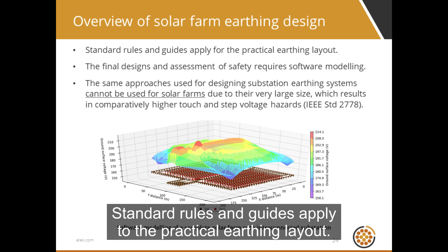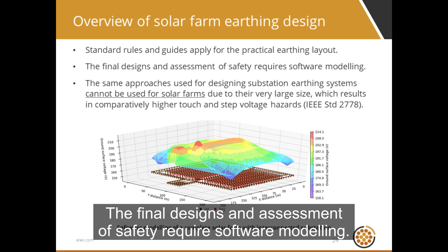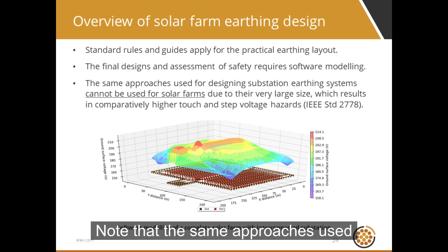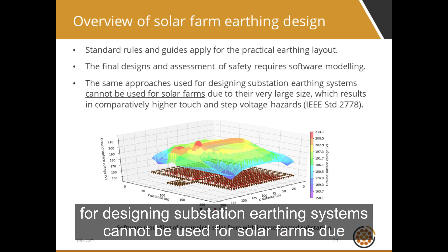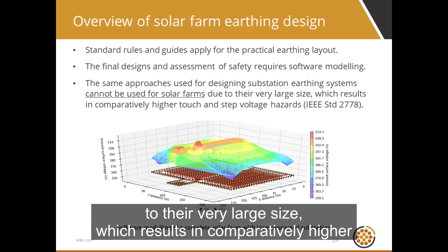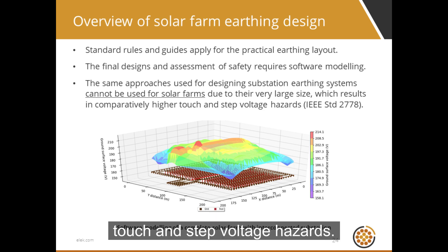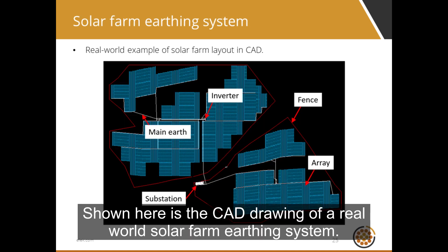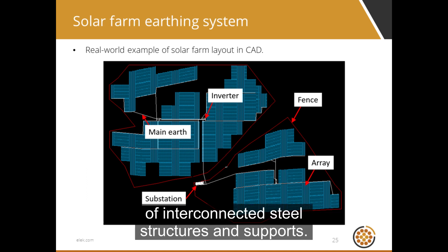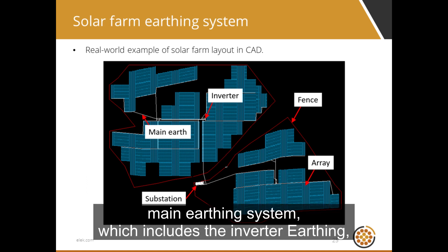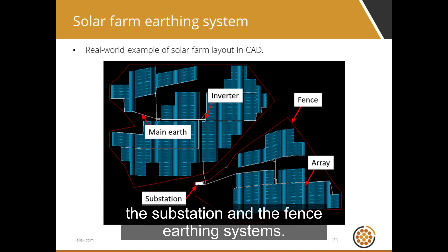Standard rules and guides apply to the practical earthing layout, and the final designs and assessment of safety require software modeling. Note that the same approaches used for designing substation earthing systems cannot be used for solar farms due to their very large size, which results in comparatively higher touch and step voltage hazards. Shown here is the CAD drawing of a real-world solar farm earthing system. The array earthing consists of interconnected steel structures and supports, bonded with the main earthing system, which includes the inverter earthing, the substation, and the fence earthing systems.